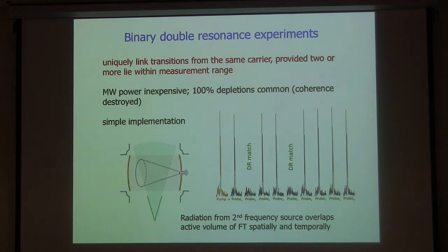You have to be careful, because when you drive the power that hard, there are potentially issues with baseline that can affect your FID, but as a practical matter we usually run about 10 to 13 dBm. That's easily produced by commercial sources of this size. Exactly, so that's the beauty. This is really almost turnkey.